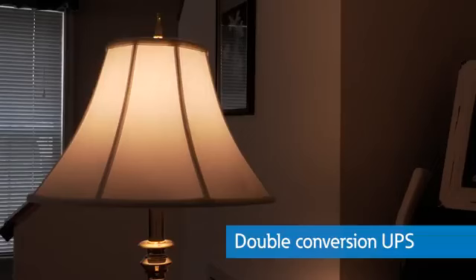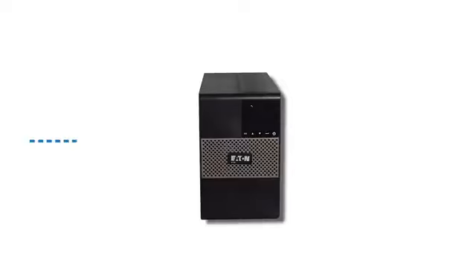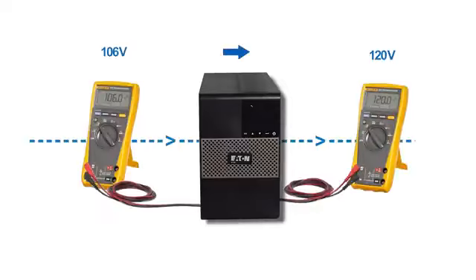If you're unsure of which type of UPS you have, you can do a simple test. Plug a light into the output and watch the light as you unplug the source. If the light flickers, you have an offline or line interactive UPS. If not, it's a double conversion UPS. To show the additional benefits of a line interactive UPS, or to distinguish it from a standby UPS, you would need a meter or variable source to show how an undervoltage or an overvoltage causes the UPS to react.